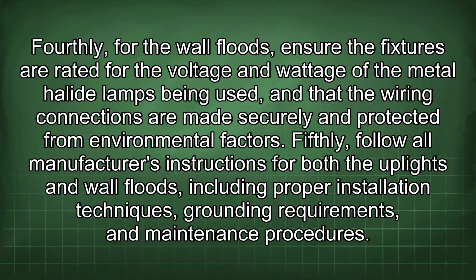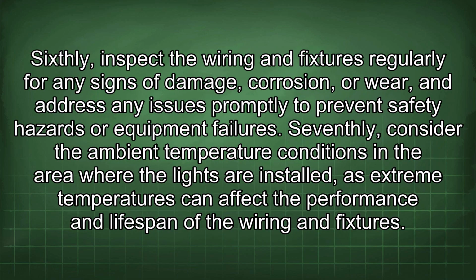Fifthly, follow all manufacturers' instructions for both the uplights and wall floods, including proper installation techniques, grounding requirements, and maintenance procedures. Sixthly, inspect the wiring and fixtures regularly for any signs of damage, corrosion, or wear, and address any issues promptly to prevent safety hazards or equipment failures. Seventhly, consider the ambient temperature conditions in the area where the lights are installed, as extreme temperatures can affect the performance and lifespan of the wiring and fixtures.